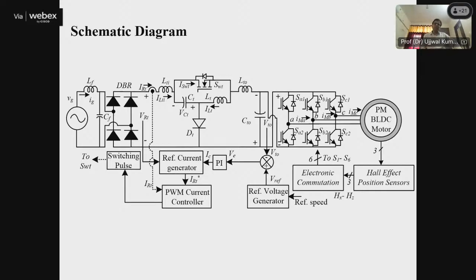So this is one advantage. The second advantage is that the switching frequency of the IGBT switches of the voltage source inverter will be very low. All these switches will operate at the fundamental switching frequency only. Therefore, the switching losses of all the IGBTs of the VSI will be reduced to a very low value, and the efficiency of the inverter will increase significantly.